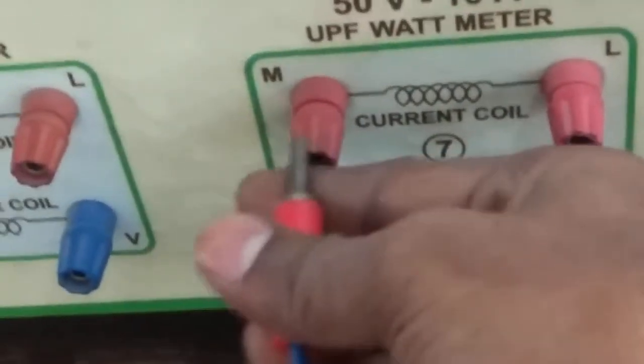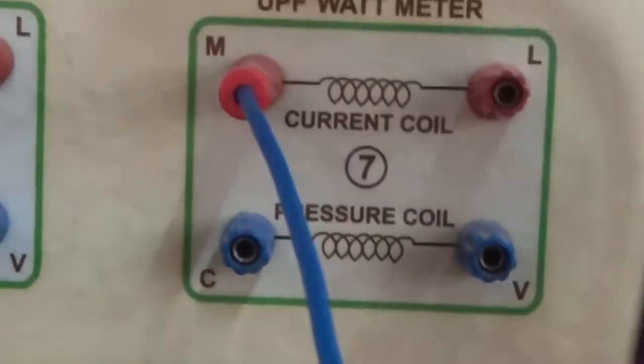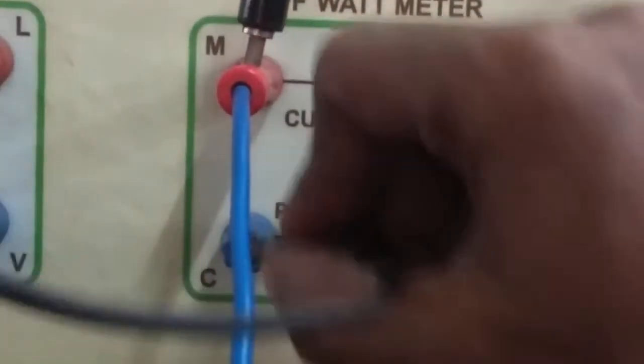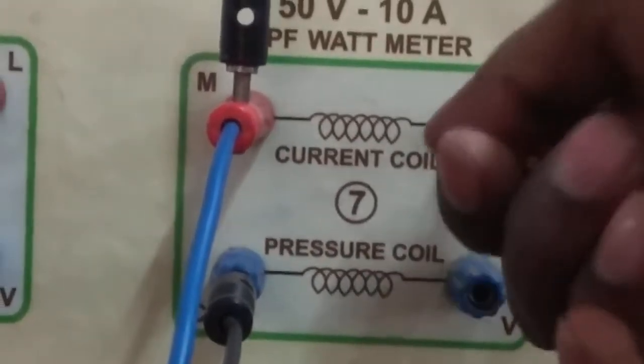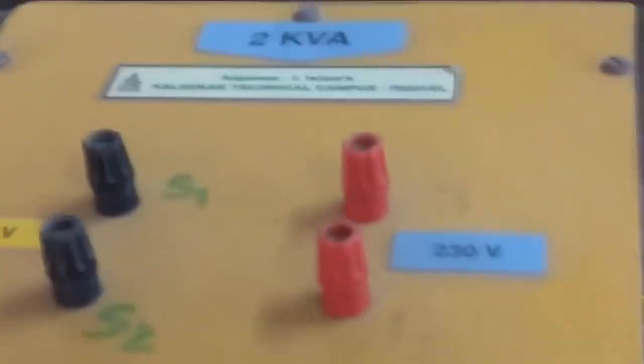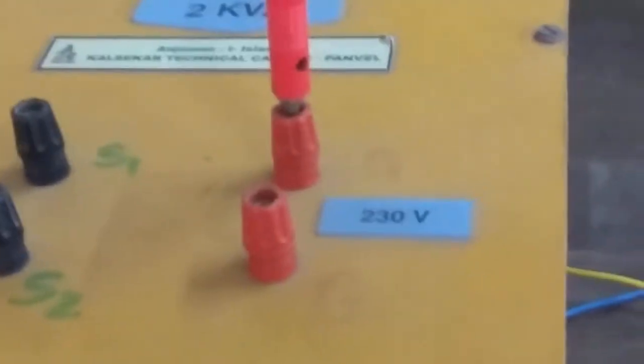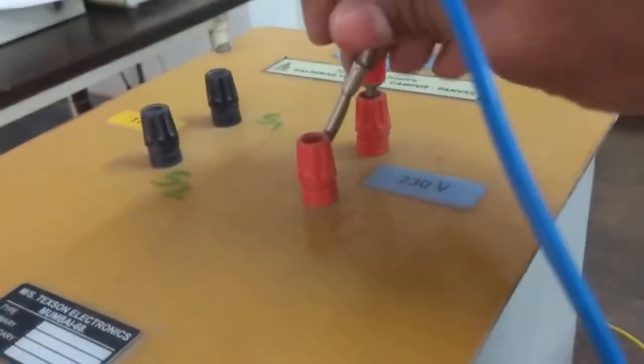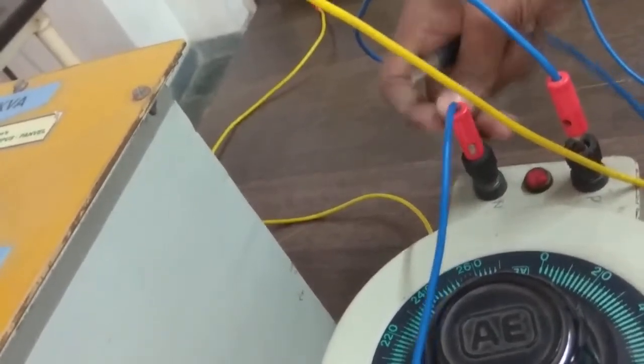Now we will connect the variac output terminal phase wire to the high range ammeter, that means the 20 ampere ammeter. And from the ammeter we will connect the wire to the high range wattmeter M terminal. In the wattmeter we will short this MC terminal, and from the L terminal of this wattmeter we will connect to the HV side of the transformer. We will connect the neutral terminal of the variac to the HV side of the transformer. Similarly, we will give the neutral from the variac to the wattmeter V terminal.